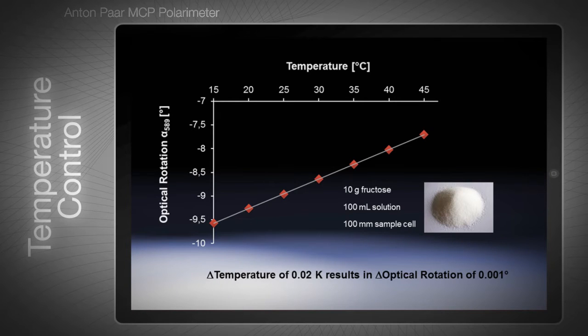For a sample of 10g fructose in a 100ml solution, for example, a temperature variation of just 20 mK changes the optical rotation by 0.001°. This is 10 times the MCP's resolution in optical rotation, so it is crucial to have the temperature precisely under control.